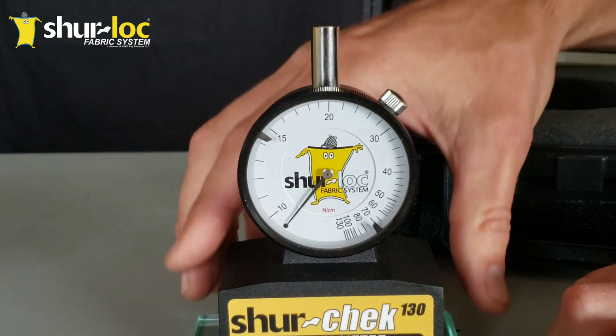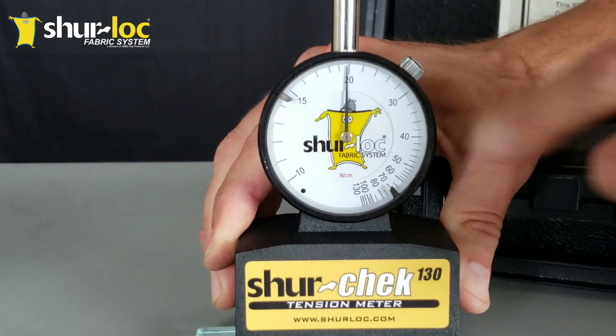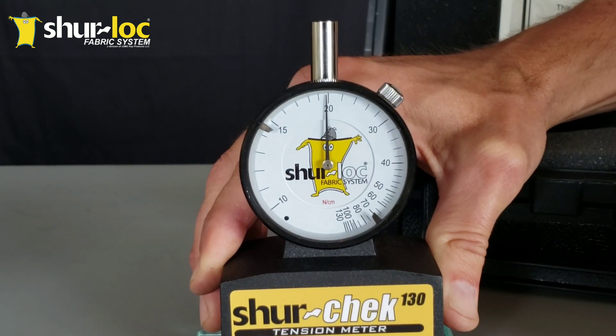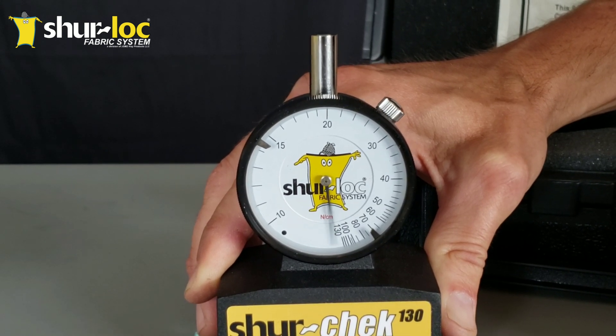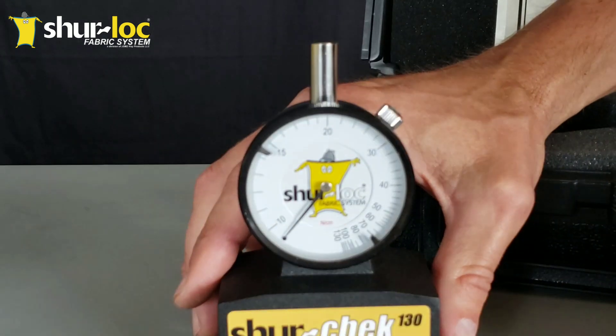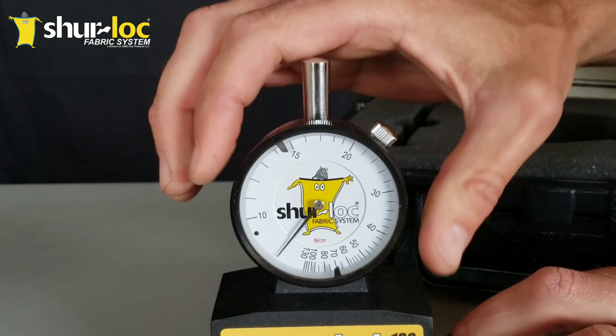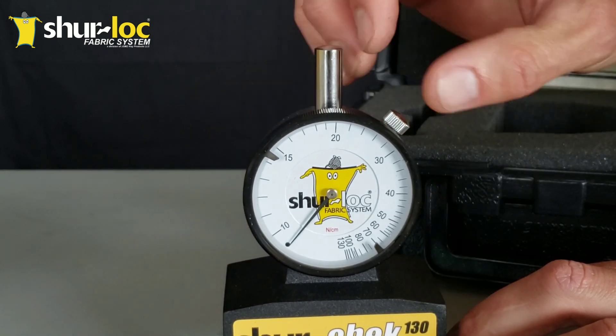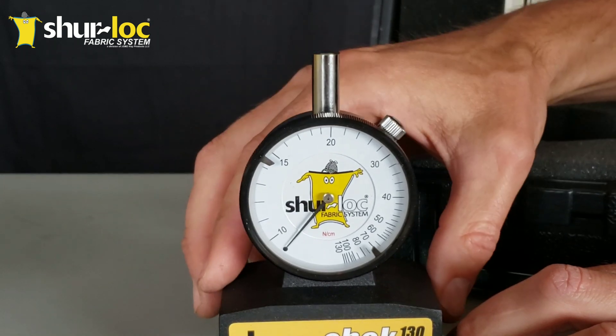If your needle is pointing at rest anywhere around the three or nine o'clock position, that's a good indicator to send it in and get it recalibrated. You should do that approximately every year anyway. Also, if you set it on the glass standard and the bezel has to be turned way out of range to zero it, that would also be a good indicator to send it in. We can help you out with that — go to shurloc.com for more information.